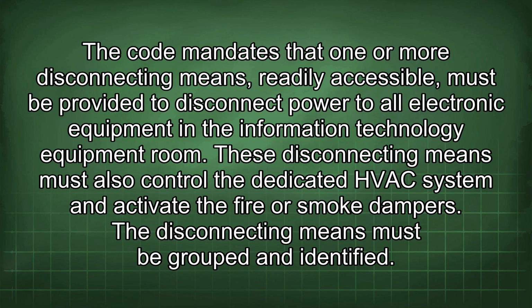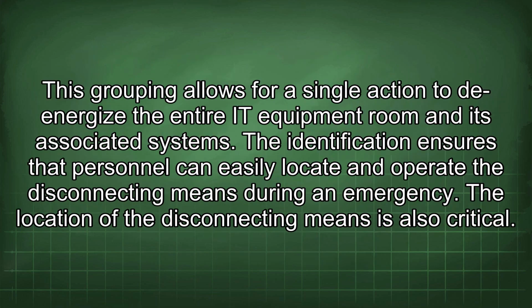The disconnecting means must be grouped and identified. This grouping allows for a single action to de-energize the entire IT equipment room and its associated systems. The identification ensures that personnel can easily locate and operate the disconnecting means during an emergency.